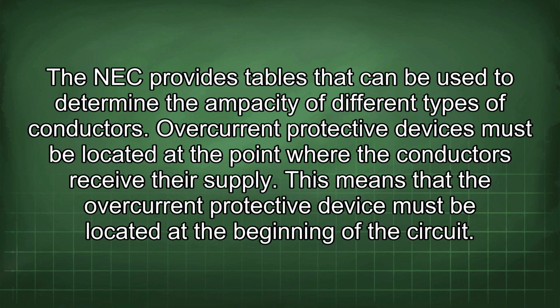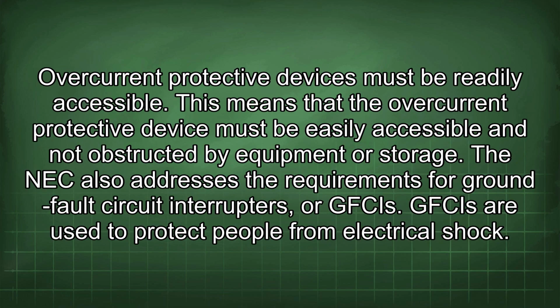Overcurrent protective devices must be located at the point where the conductors receive their supply. This means that the overcurrent protective device must be located at the beginning of the circuit. Overcurrent protective devices must be readily accessible. This means that the overcurrent protective device must be easily accessible and not obstructed by equipment or storage.